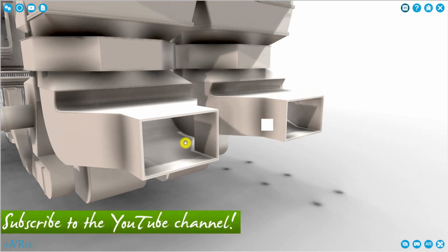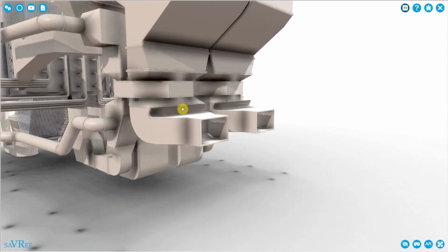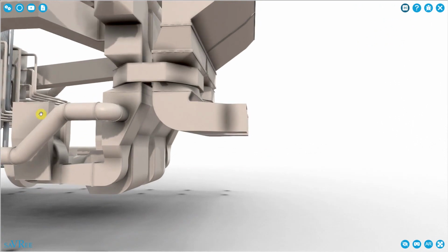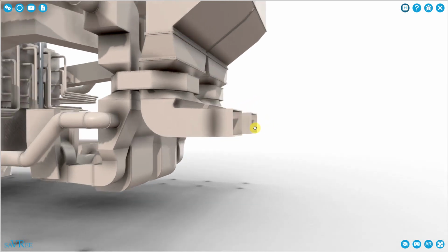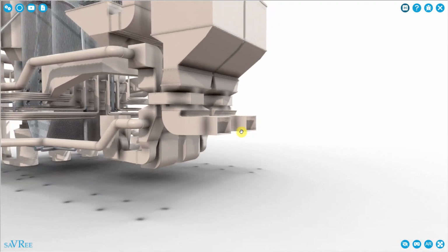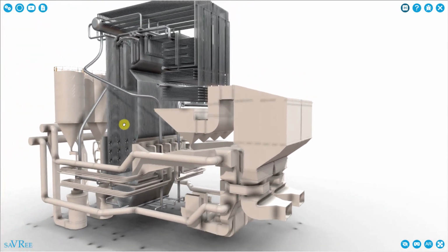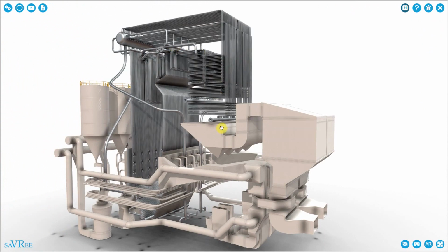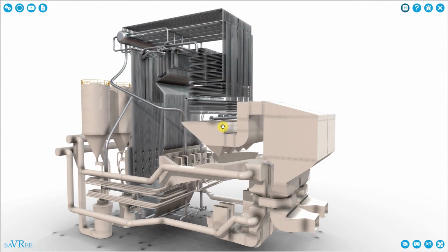ducts here. We're actually going to draw the exhaust gases out of the boiler using an induced draft fan, although this really depends upon the design of the boiler. Induced draft simply means that we're drawing the process air in on one side and blowing it out of the other. Our process gas in this case is gas from the water tube boiler. So we've got the fly ash, this light ash, coming through the boiler. And then what we could do, we could just send that up through a chimney, or what we call a stack, and then we just blow it out into the atmosphere.